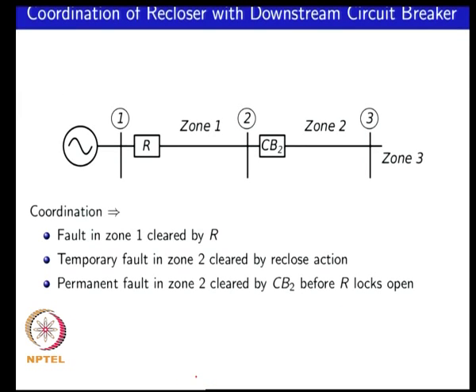Next we look at coordinating between a recloser and a circuit breaker, with an upstream recloser and a downstream circuit breaker. The recloser might be sitting at the substation and the circuit breaker further downstream. The recloser logic may also incorporate an underlying circuit breaker characteristic in addition to its reclosing behavior. The circuit breaker in this arrangement can be coordinated with CB2 as previously discussed.